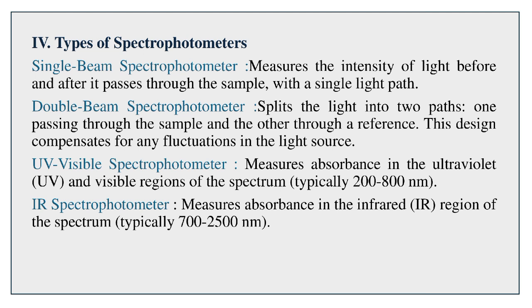This double-beam design compensates for any fluctuations in the light source. UV-visible spectrophotometer measures absorbance in the ultraviolet (UV) and visible regions of the spectrum, typically 200 to 800 nanometers. IR spectrophotometer measures absorbance in the infrared (IR) region, typically 700 to 2,500 nanometers.